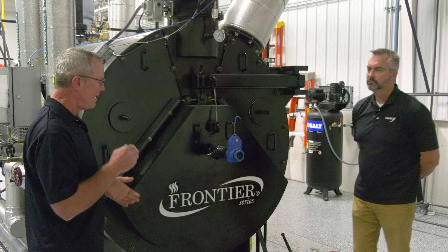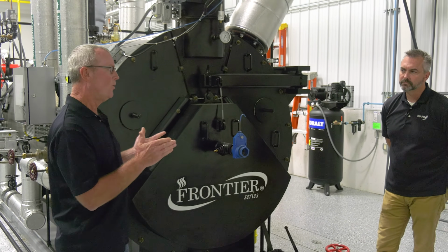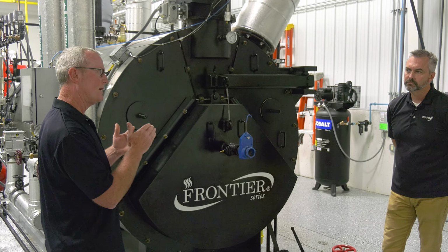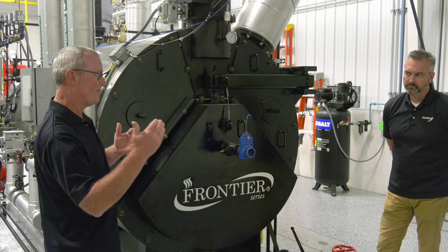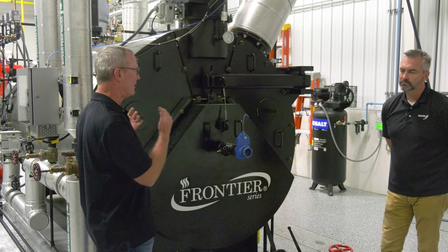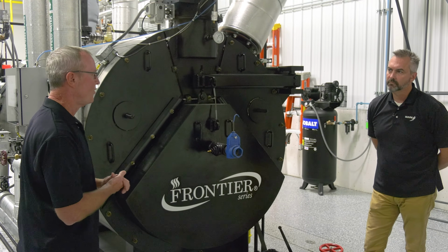And again, if you monitor that and write that down every day in your boiler log, then you know before you ever have a problem. Hey, my stack temperature's been running 430, 435. Now we're at 450. There's a problem. We need to take a look and see what's going on. If it's not on the combustion side, I'm scaling the boiler up. I've got to get that fixed before I do damage to the boiler.